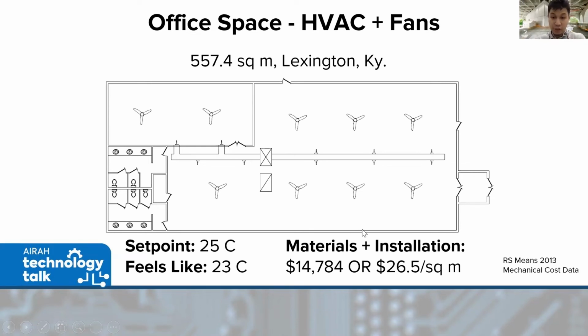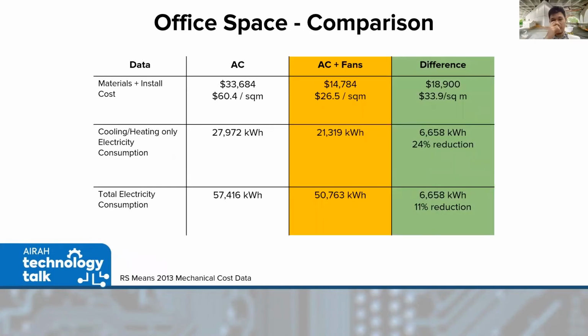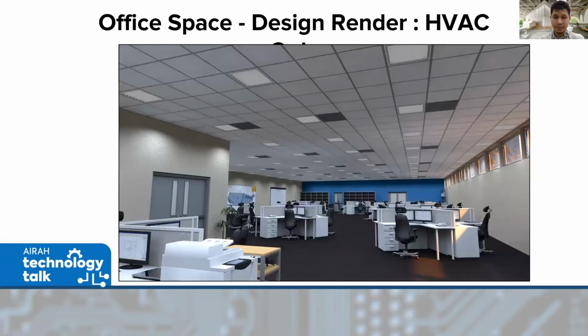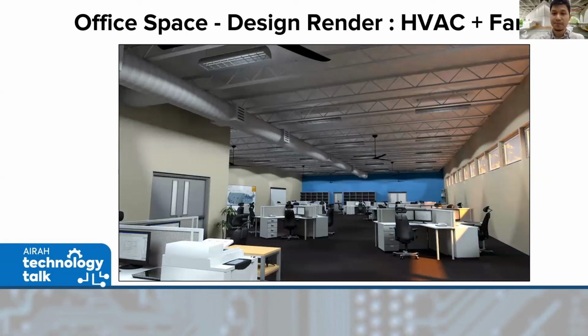The material installation drops by more than half. So that is not bad. And this is the comparison. There's about a $19,000 difference between the cost of AC and AC with fans, and then a 24% reduction in consumption for cooling and heating only, and 11% reduction in total electricity consumption. And this is the design render for that office space with HVAC, and this is with fans.